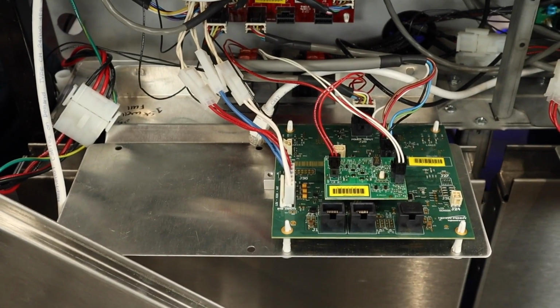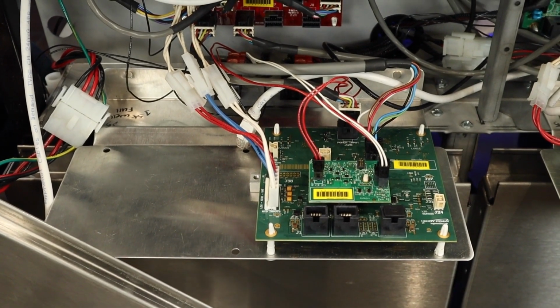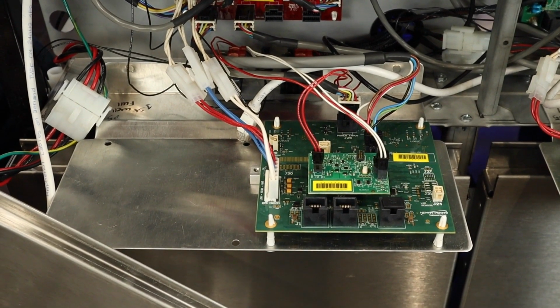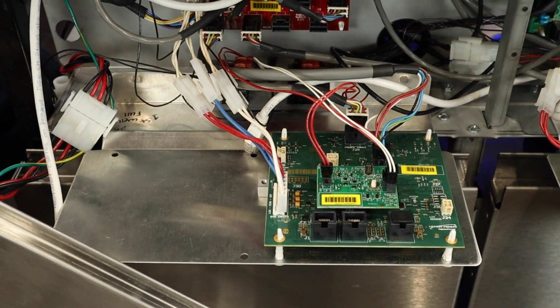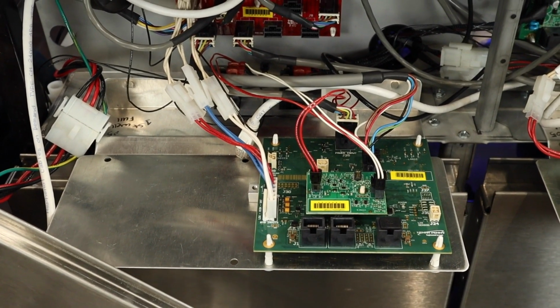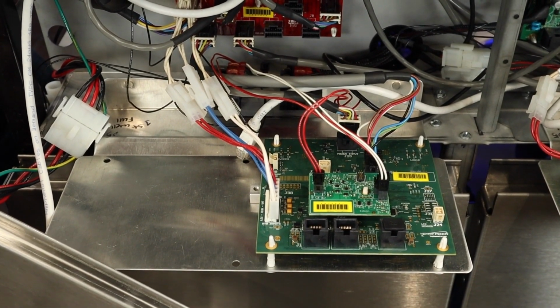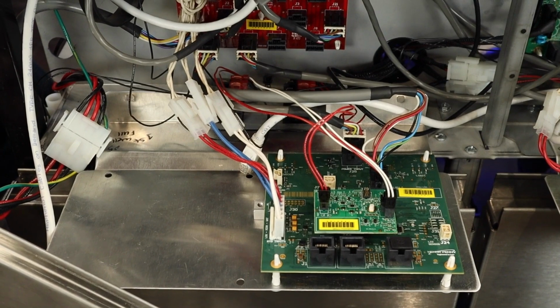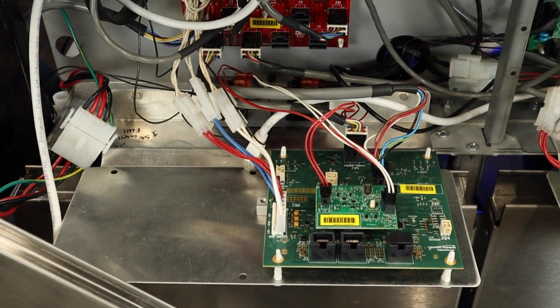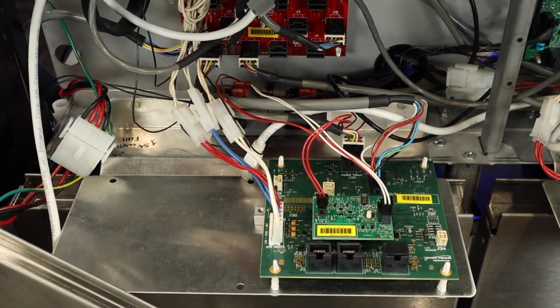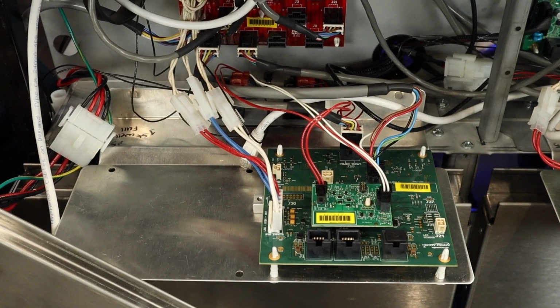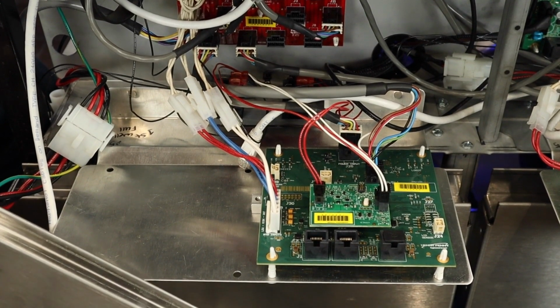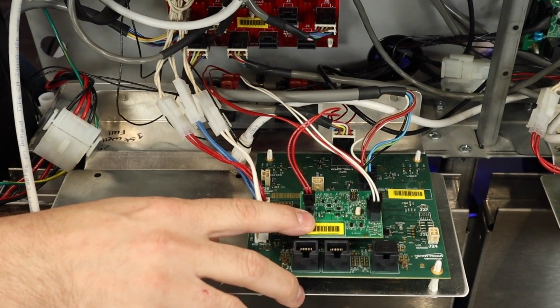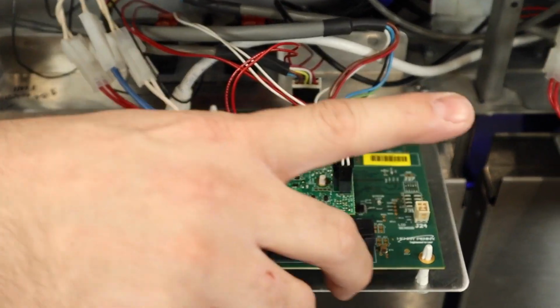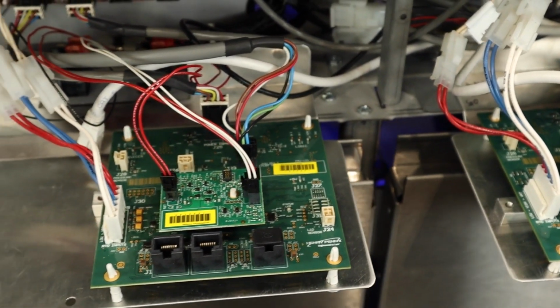For a high limit that is intermittent, we suggest making sure the probe is clean and clear of carbon buildup first. Then make sure it is securely fastened and check all connections at the PMU board. If that still doesn't take care of it and we have checked our probe for resistance and it is properly calibrated, then we could try swapping the PCB for the high limit to another VAT to see if that problem follows.